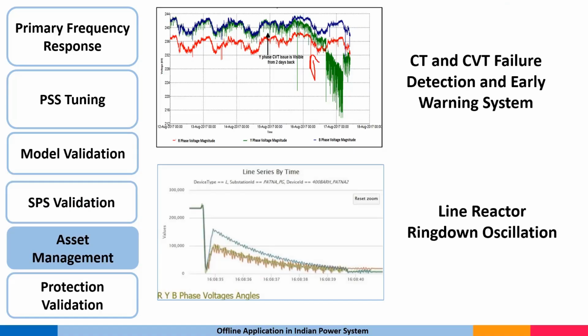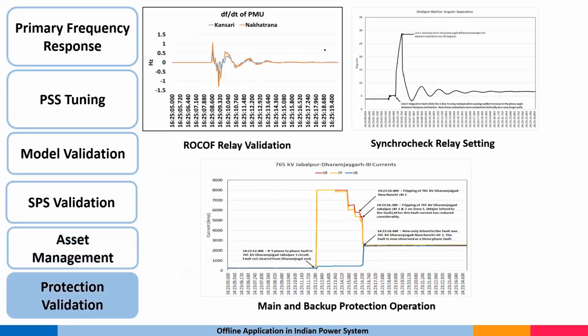So first we tried to ask the site to check the information, whether there was any loose connection. There was no loose connection. Then we told them that their CVT needs to be checked. The CVT was providing very erroneous data and was on verge of failure, but it was avoided by the substation, which also observed some leakage. So this kind of support can be provided from the control center to the respective site.